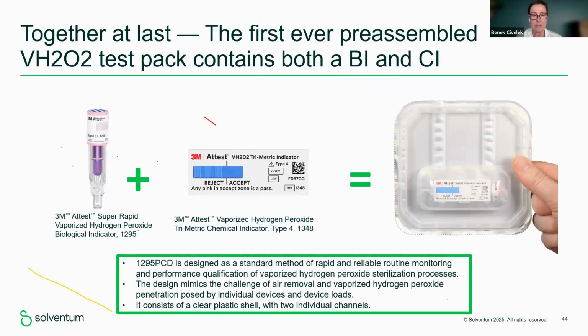In this design, we are aware of the 1295, and this is dedicated for hydrogen peroxide sterilization, and it has the reduced time technology. Also, we have talked about the hydrogen peroxide trimetric indicator, which is type 4, and these are brought together inside the shell. And as you can see here, it has two channels.